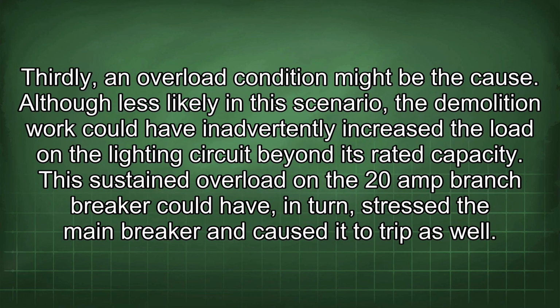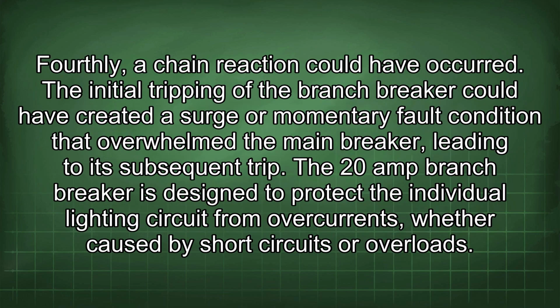Thirdly, an overload condition might be the cause. Although less likely in this scenario, the demolition work could have inadvertently increased the load on the lighting circuit beyond its rated capacity. This sustained overload on the 20-amp branch breaker could have, in turn, stressed the main breaker and caused it to trip as well. Fourthly, a chain reaction could have occurred. The initial tripping of the branch breaker could have created a surge or momentary fault condition that overwhelmed the main breaker, leading to its subsequent trip.